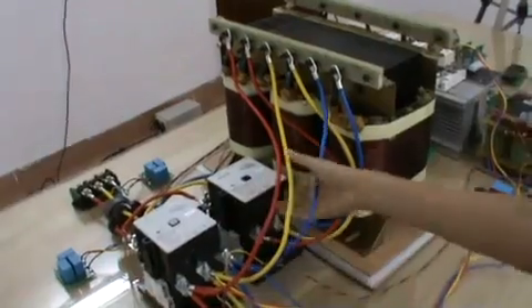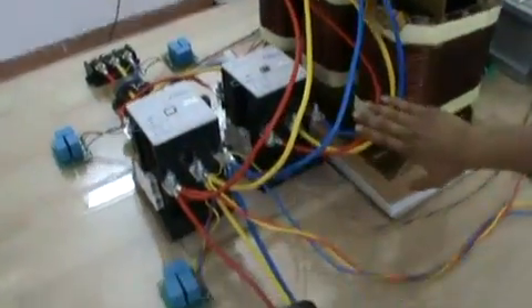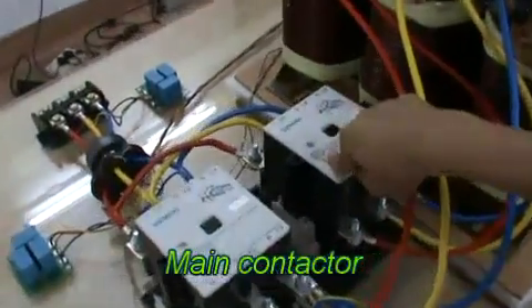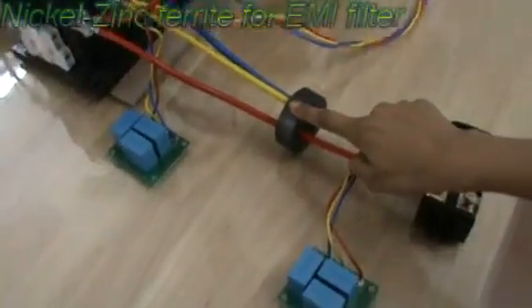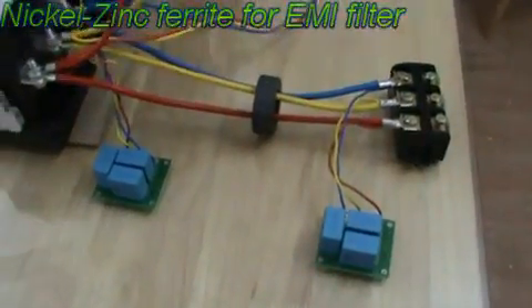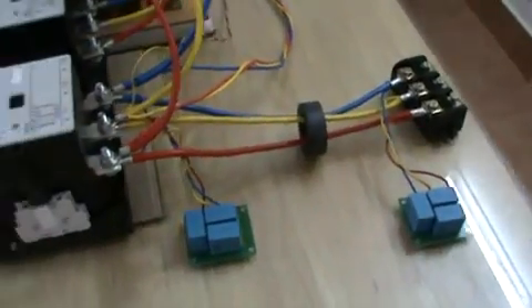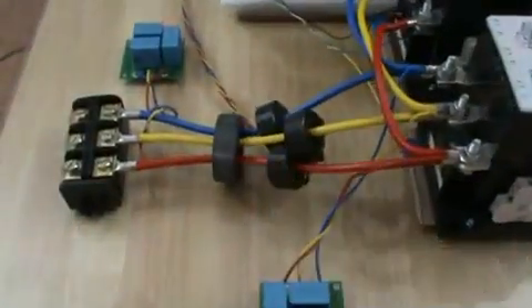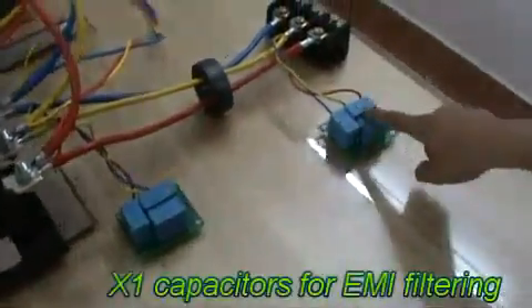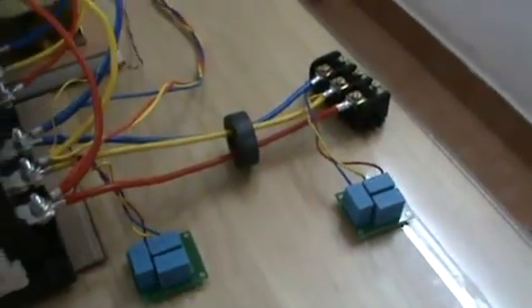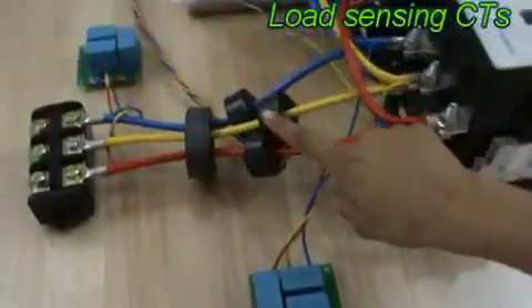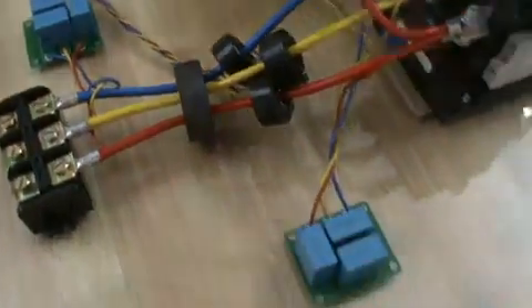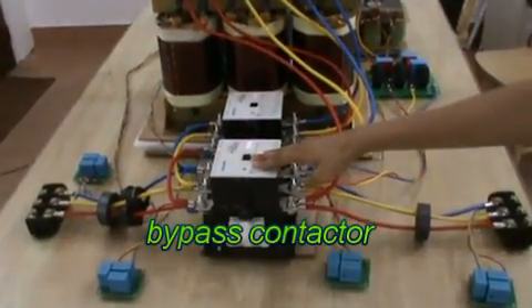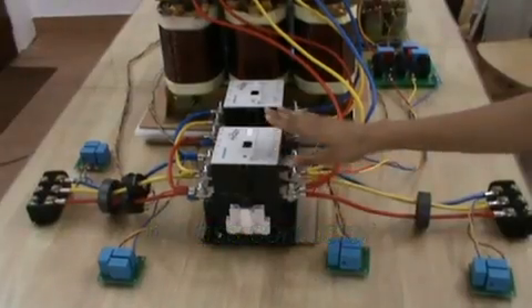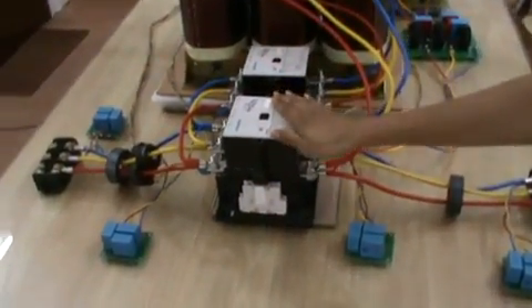This is the AC input. This is the output. The output is connected through a contactor. This is a nickel zinc ferrite core for EMI filtering used both at input and output. These are X1 capacitors used for EMI filtering. These CTs are for sensing the output current. This is the bypass contactor. In case of overload or high temperature or any hazardous condition, the unit will bypass without interrupting the output.